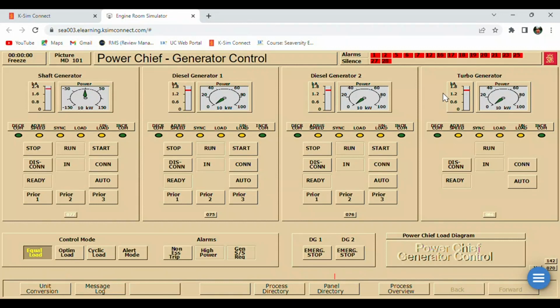In this scenario, we are just going to start the emergency generator and then connect it to the emergency bus bar. Afterwards, we need to start also diesel generators number 1 and 2, and then connect them to the main bus bar. So let's start. Now it is still in a freeze condition. We need to start it by clicking this blue button and then click play. Now it's running.